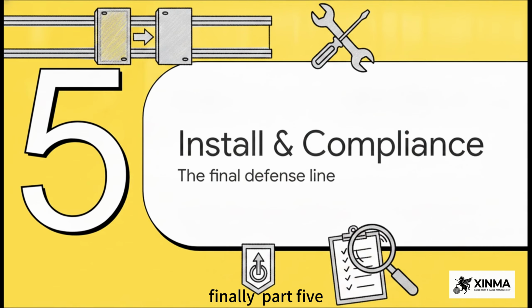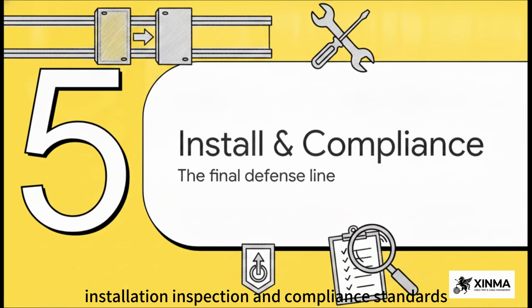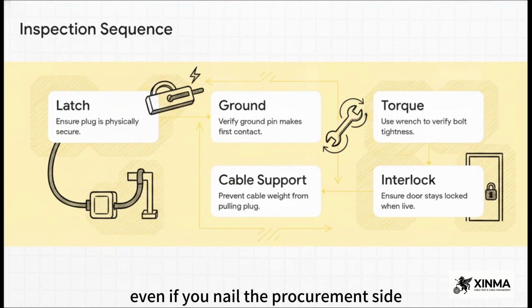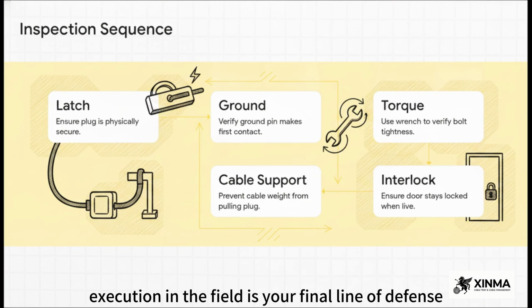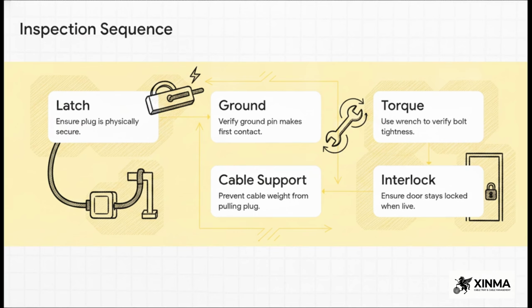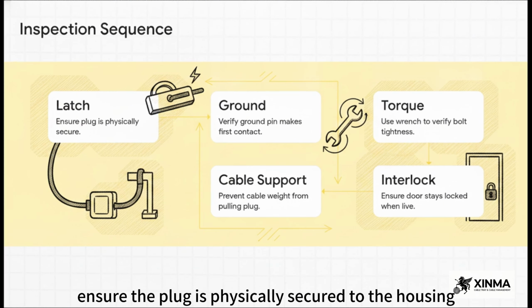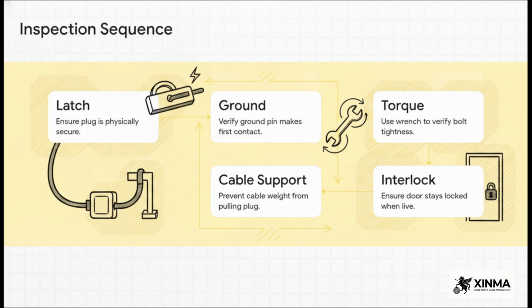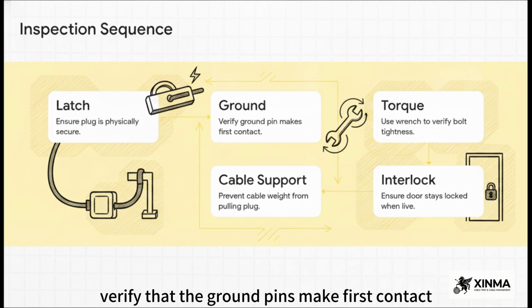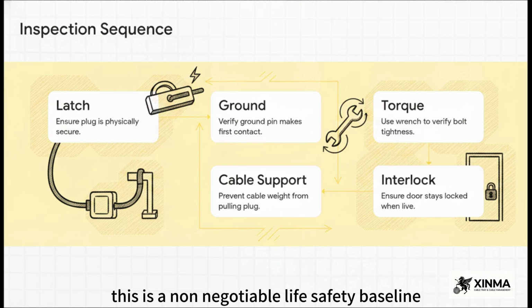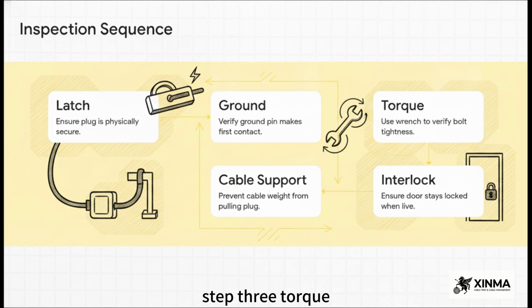Finally, Part 5, Installation, Inspection, and Compliance Standards. Even if you nail the procurement side, execution in the field is your final line of defense. Here is the mandatory 5-step installation inspection sequence. Step 1. Latch. Ensure the plug is physically secured to the housing. Step 2. Ground. Verify that the ground pins make first contact. This is a non-negotiable life safety baseline. Step 3. Torque. You must use a calibrated torque wrench to verify bolt tightness.